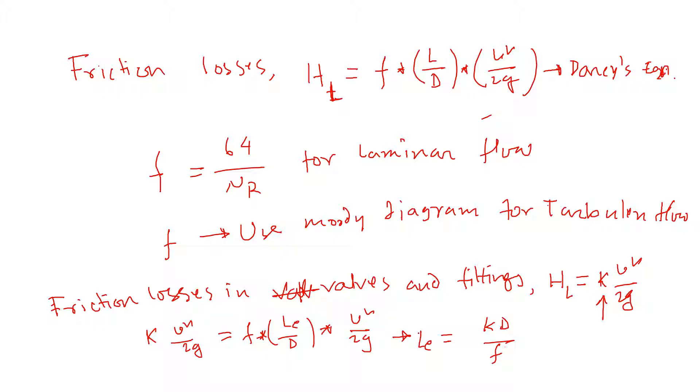Most of the time this equation is used. Once we find the total length of pipes plus the fittings length, add them all up and use that in Darcy's equation to calculate the friction losses.